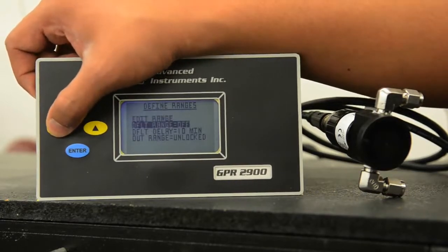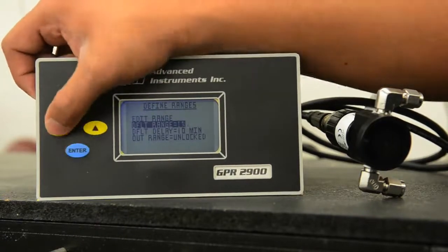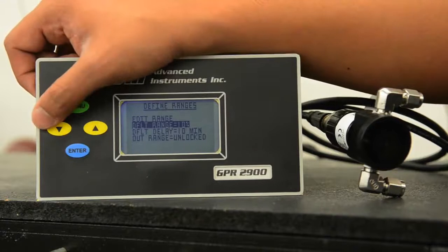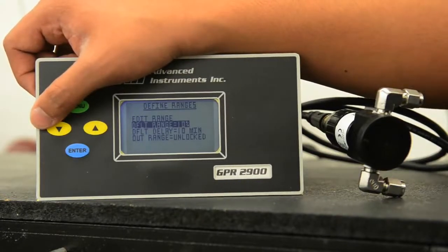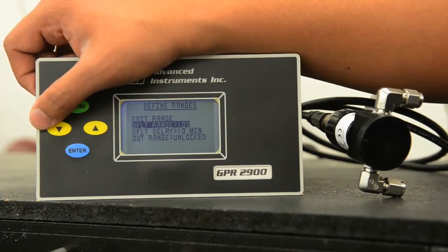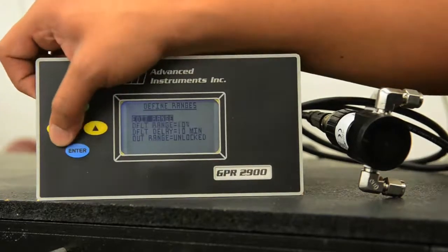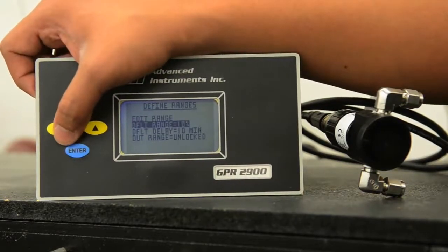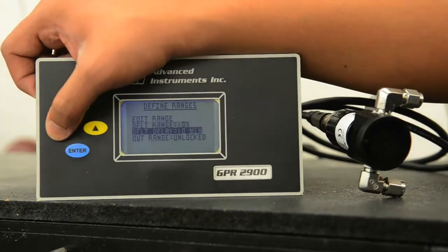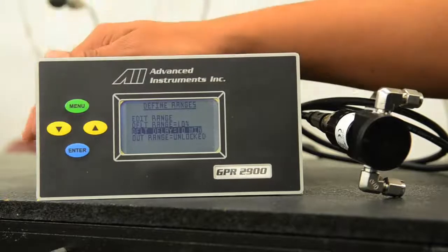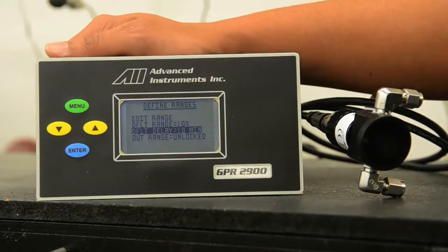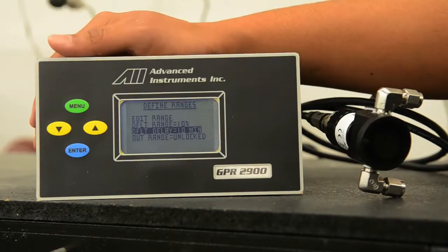We also have the option for a default range. A default range is the option if you would like the analyzer to default to a range when no key press is selected within a certain amount of time. This is ideal if you are configuring the analyzer and would like to have your range set at, say, 10% to have your 4 to 20 line up to the 10% range. The default delay is currently set at 10 minutes, so within 10 minutes of no key presses, the range will automatically switch to the 10% range. Again, this is ideal if you have service technicians working on the analyzer and you would like to ensure that the range of interest is set once they are done with the analyzer.